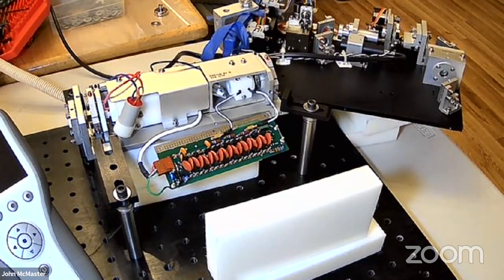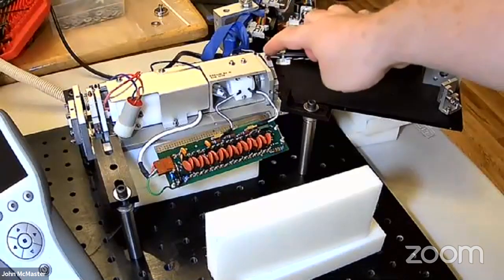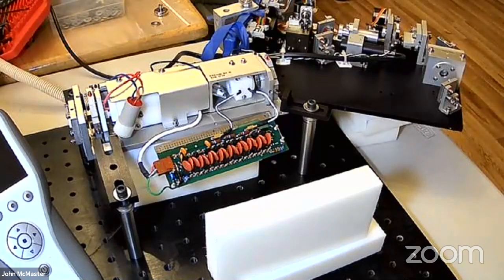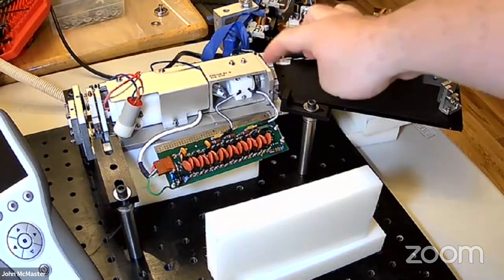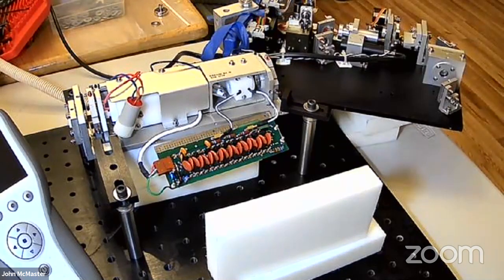Okay? Mm-hmm. So by rotating it that way, and then after inserting this, we will make the XY adjustments here to then optimize the laser power. We're able to correct the aberrations that this polarization plate introduced into the beam, and then get it realigned to the beam path.